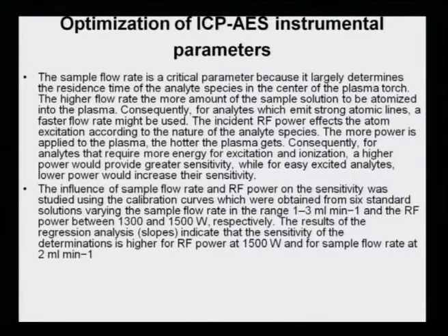And what are these parameters? The incident RF power affects the atom excitation and will also depend on the nature of the analyte species. More power will be applied for the plasma to get hotter, so that more energy can be provided for excitation and ionization, and greater sensitivity can be attained.